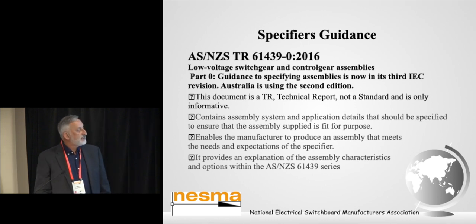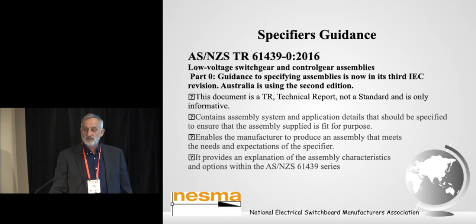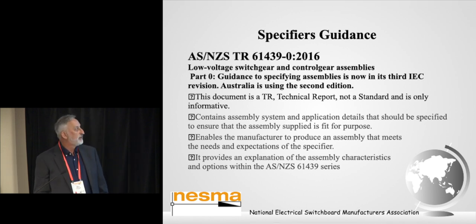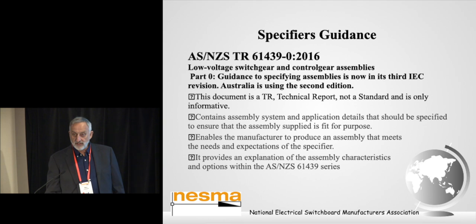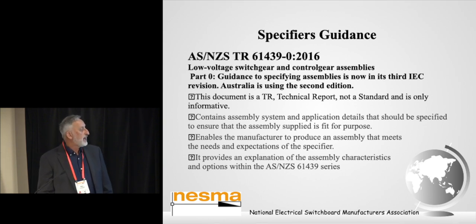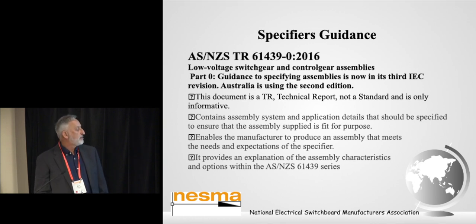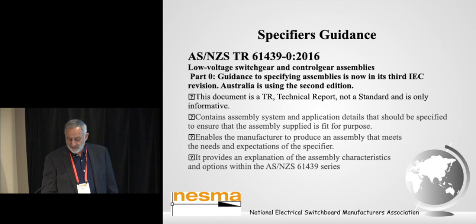So there is another document which comes to the fore with the 61439 series, and that's called the Part 0. Australia has adopted that. It's AS/NZS TR, meaning a technical report, and so it's not a standard and it's informative only. But what it does do, it contains assembly system and application details that should be specified to ensure that the assembly supplied is fit for purpose. It enables the manufacturer to produce an assembly that meets the needs and expectations of the specifier, and it provides an explanation of the assembly characteristics and options within the 61439 series.